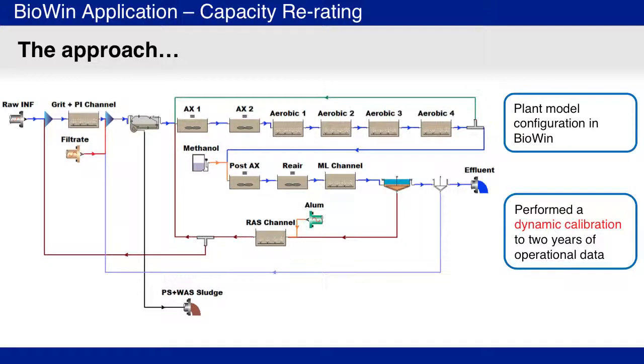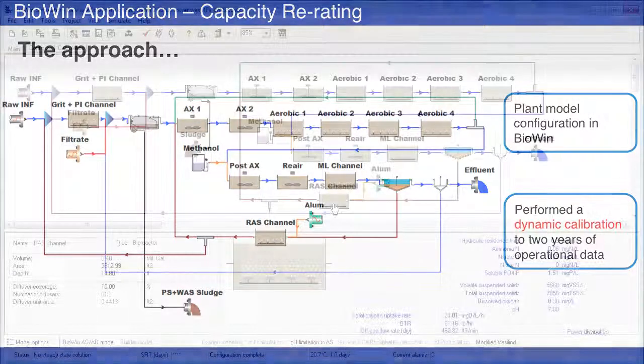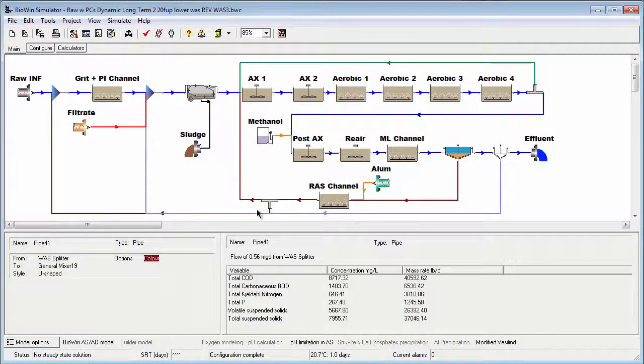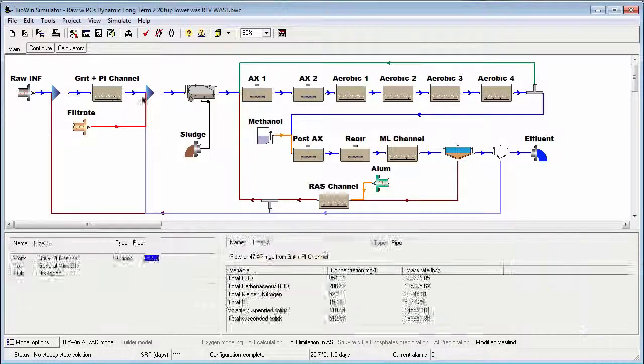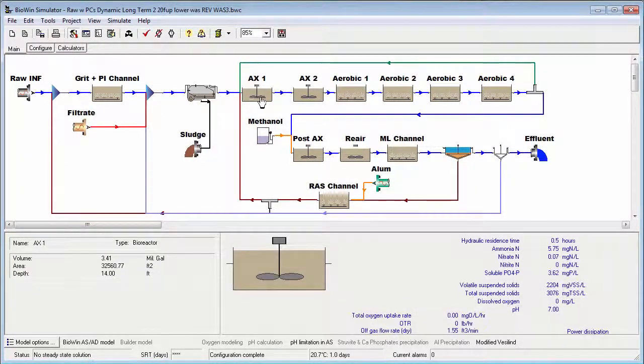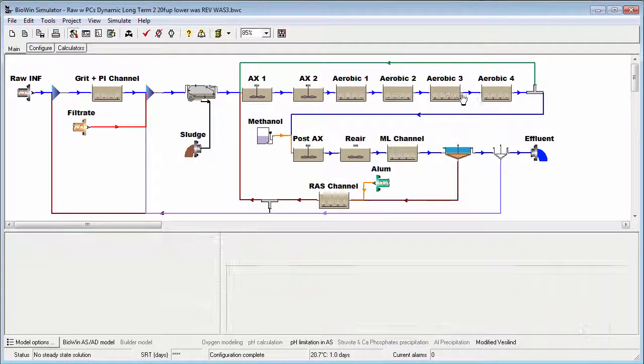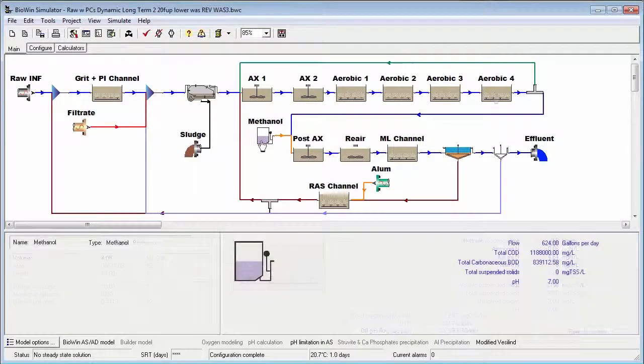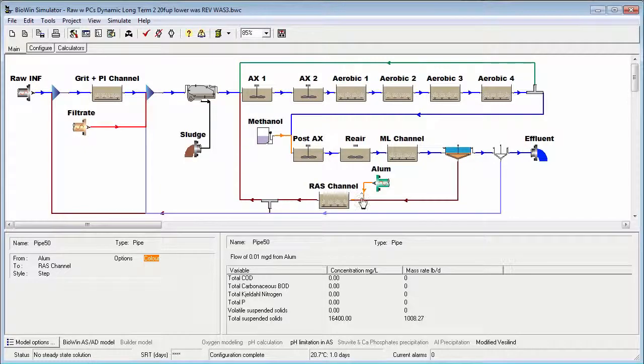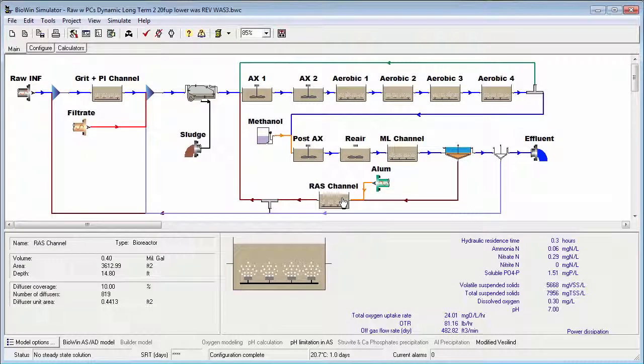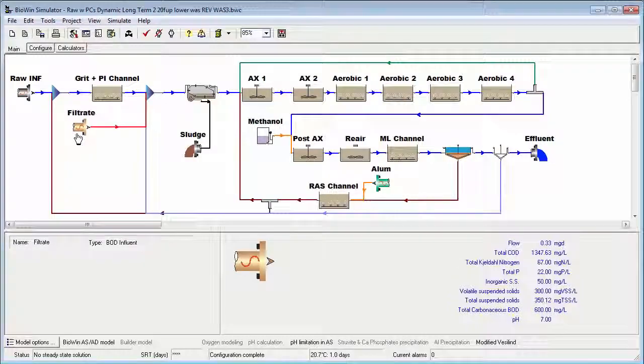The approach used was to set up a BioWin model of the treatment process. Some aspects of the BioWin model include: waste-activated sludge was directed to the primary clarifier for removal; the primary anoxic and aerated zones were modeled as several reactors in series; methanol was added to the post-anoxic zone; alum was added to the return-activated sludge channel for phosphorus precipitation; and the impact of time-varying return streams was incorporated into the model.